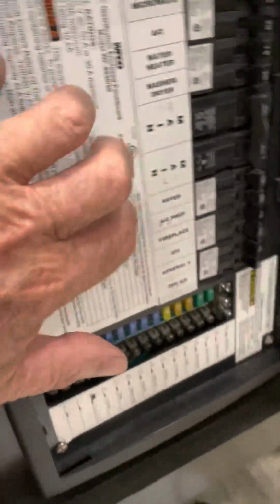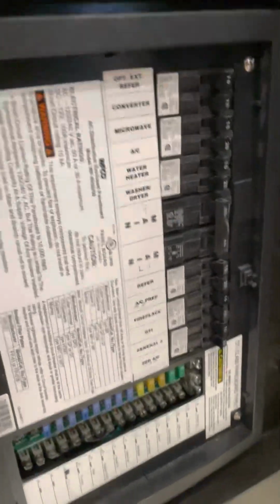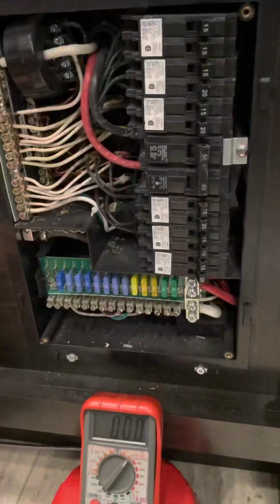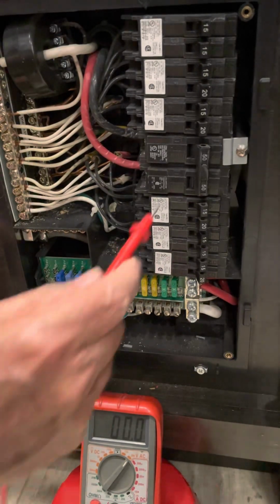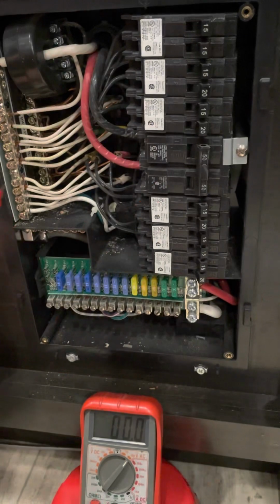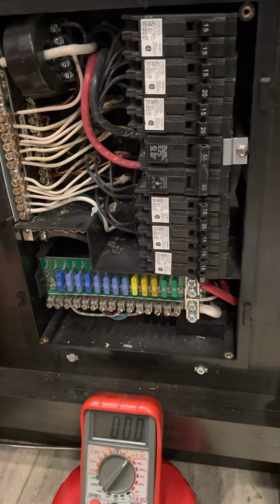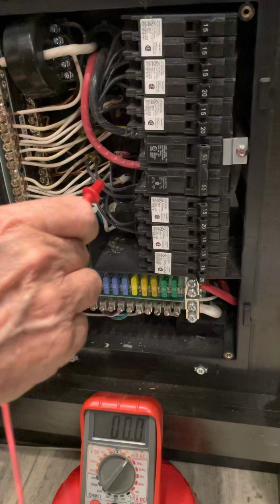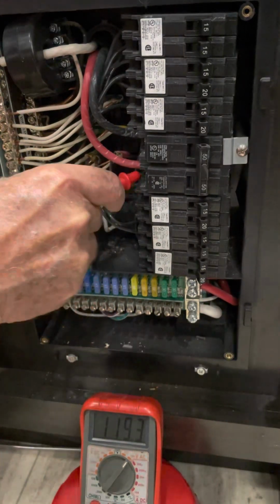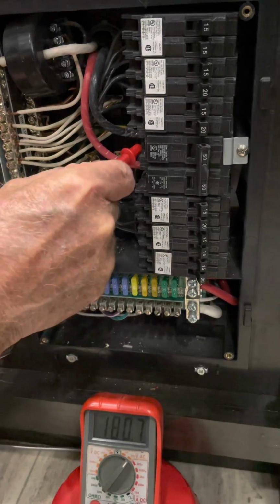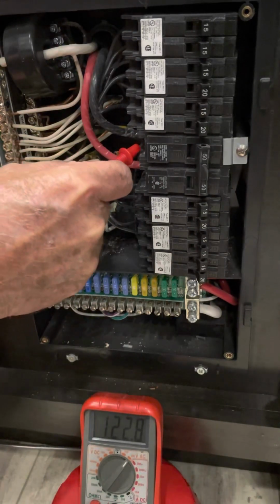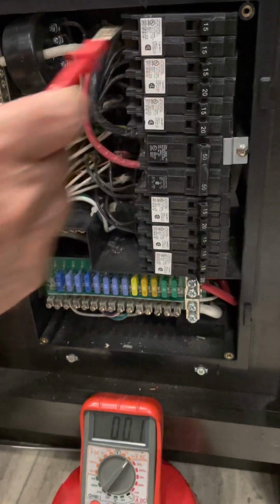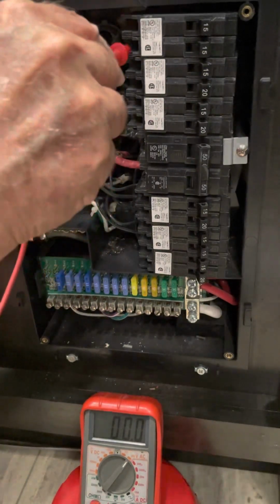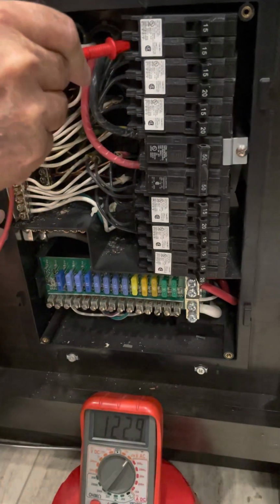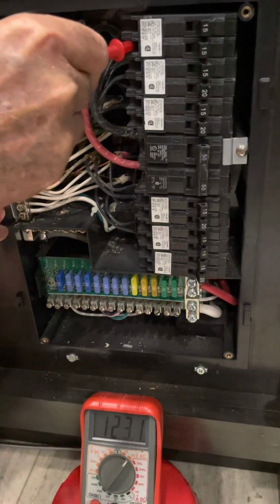You'll need to remove this cover so that you can get access to the circuit breakers. To verify that we have power inside the main circuit breaker panel, these are the two main breakers. This is your neutral bar. So we're going to measure between neutral and each big breaker. There's 120 volts. There's 120 volts. I know that my second breaker is the breaker for my converter. So I want to verify that I actually have power going to my converter, and I do.